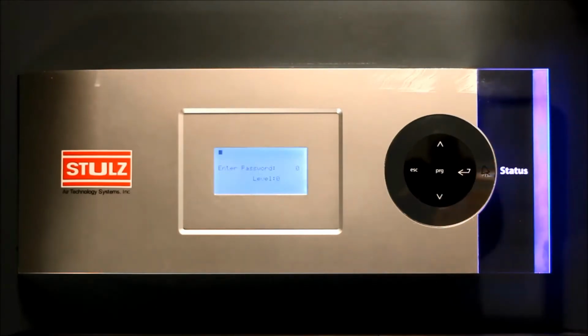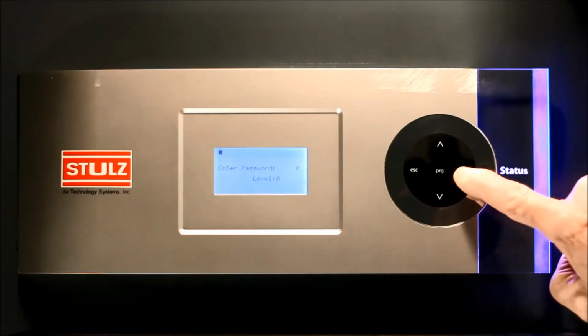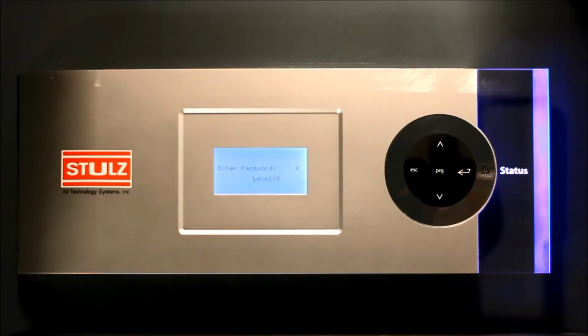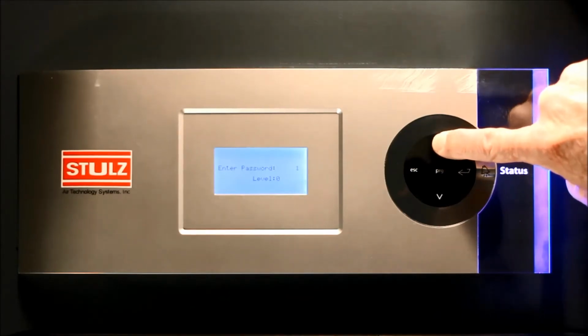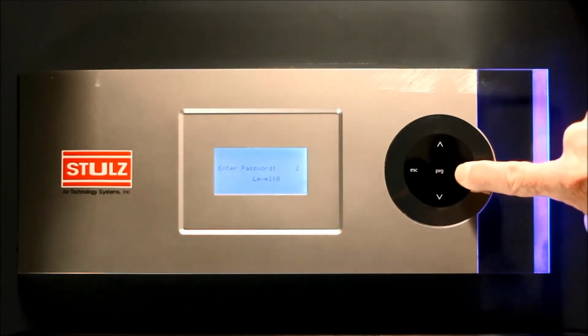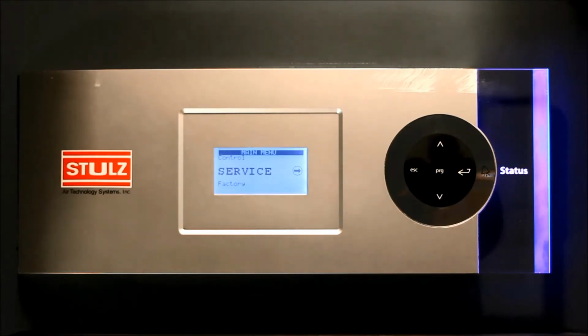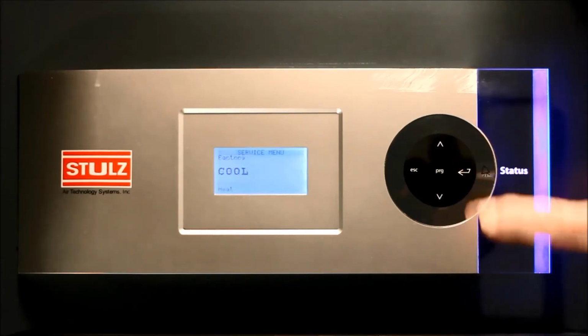The next screen will ask for a password to be entered. By pressing the enter key, we move the flashing cursor into position. Now using the up arrow, we change the password to the number 2 and then press enter. The word service will appear in the middle of the display screen again. We then press the enter button once more to access the service submenu.